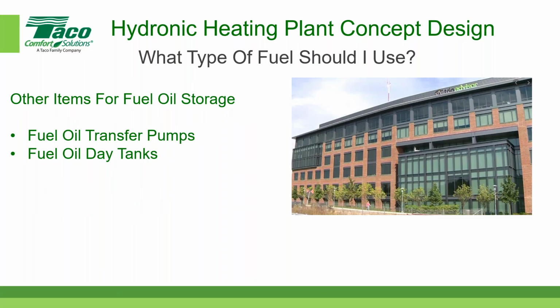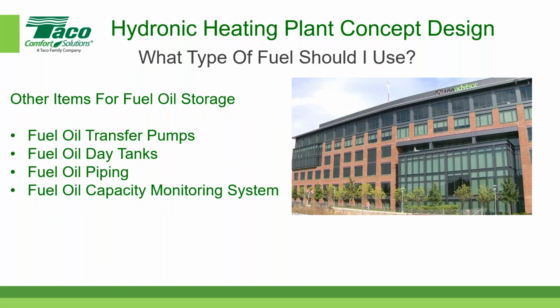If somebody needs some input into what that's all about, why don't you pop in a question and we'll take the time to answer that. Now you have the fuel oil piping, and a fuel oil capacity monitoring system. You also have to have a fuel oil leak detection system. And this is where, as I said at the very beginning, the codes come in, because every community has a different set of criteria for storing fuel oil these days. Basically, the criteria that most municipalities are developing or have developed is to keep your eye on the quality of the fuel oil storage system to make sure it's not leaking and going into the subsurface ground and contaminating the water supply and so on. So that's very, very important.